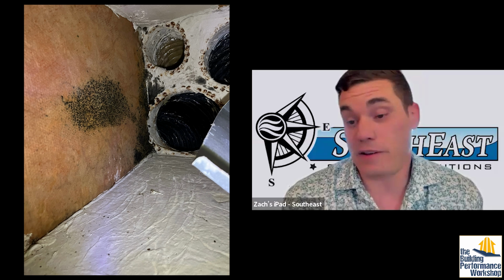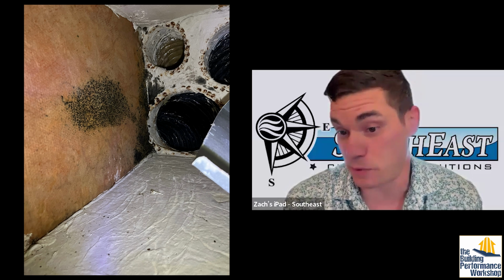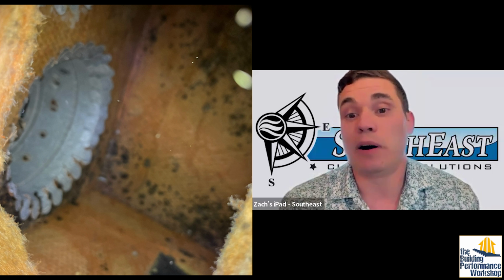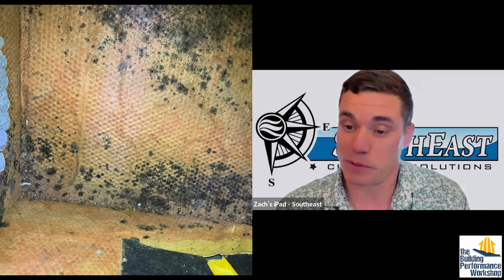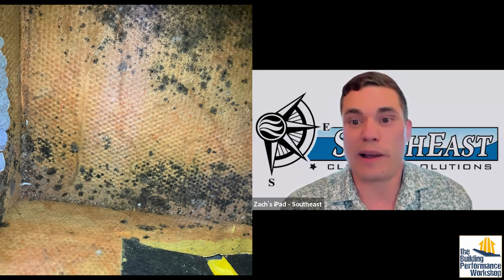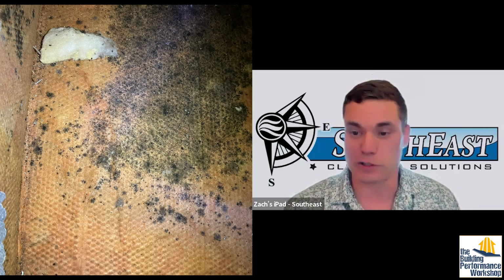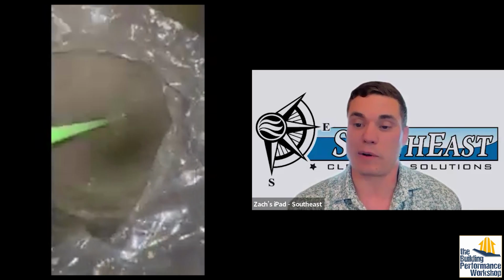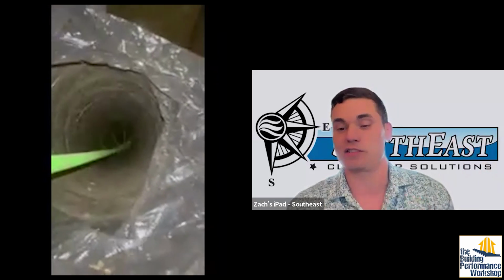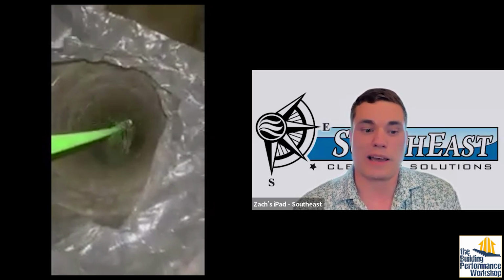So depending on the access to that ductwork, we have in Richmond a lot of attic and crawl space access. If it's between floors, I can clean it, but it's going to be difficult to clean between floors. The way that I would go about cleaning something like that first would be using an air whip to loosen most of what's on the surface. But then I'm probably going to have to, we have fiberglass rods and there's a wiffle ball attachment with water rags on it. So I zip tie the rags onto the wiffle ball attachment and push it through almost like a softball so that I actually get a contact clean on that. But that's going to be very expensive.